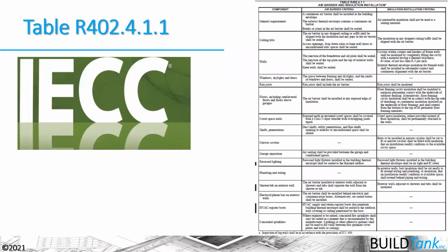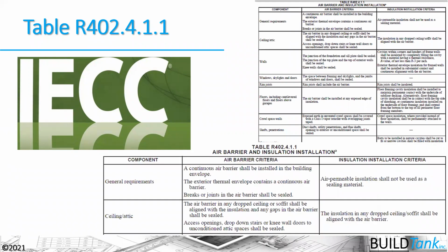So the table R402.4.1.1 is the air barrier and insulation table. That table defines the different components of the house down the left-hand side of the column there. It gives us additional criteria or specifications for how to install and where to install air barrier systems that go beyond the manufacturer instructions. And in the same way, it gives us additional installation criteria for insulation in these different components.